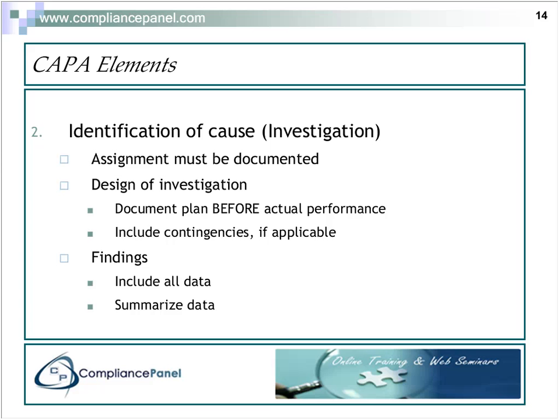When it comes to findings, include all of your data in your investigation, even to the rawest level. Also, having said that, include a summary of your data. This is going to be more for the FDA or your notified body than for any other purpose. What I found in my years of experience is that if I'm performing an investigation, I am so intimately involved with it when I perform it, I know exactly what all this data means.